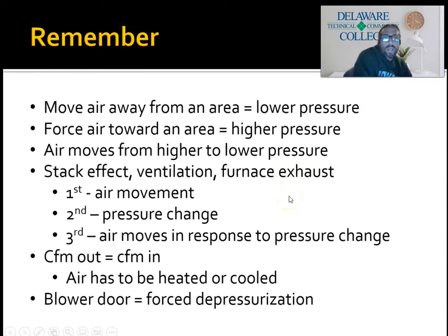So as a quick reminder from the previous lesson, remember that we're constantly dealing with air pressure changes inside of buildings. We have the stack effect, we have wind effect, we have combustion effects where the furnace is removing air from the building, we have ventilation fans. And just remember that anytime you move air away from an area, it lowers the pressure. Anytime you move air toward an area, you increase the pressure.